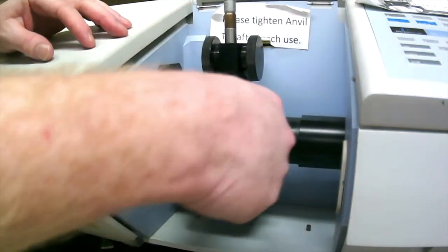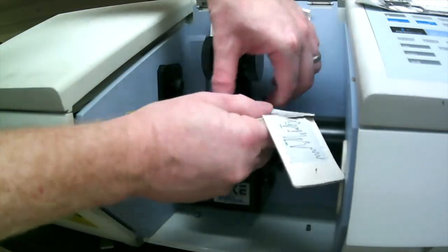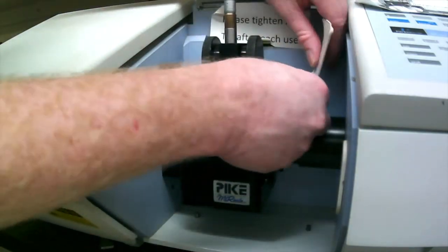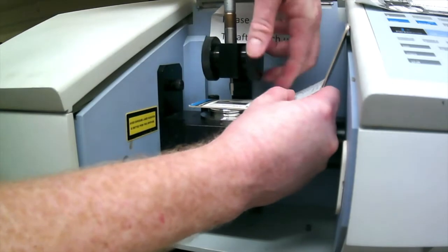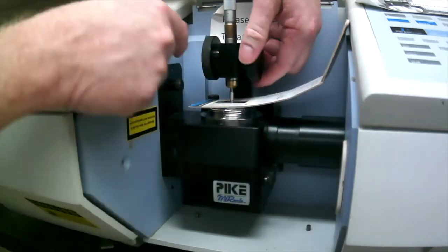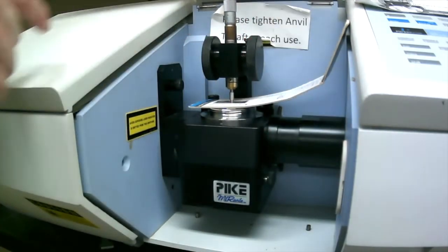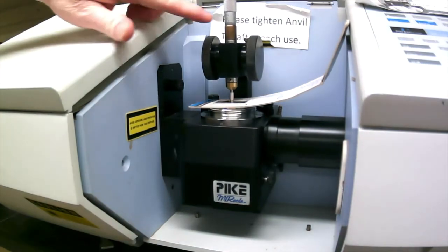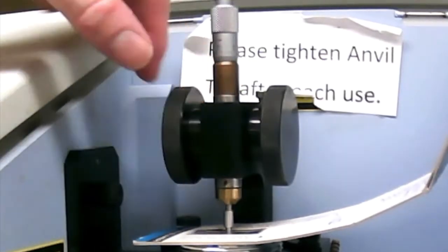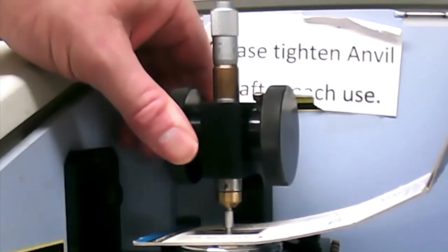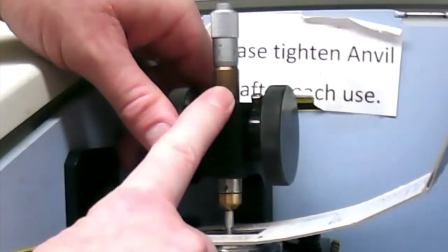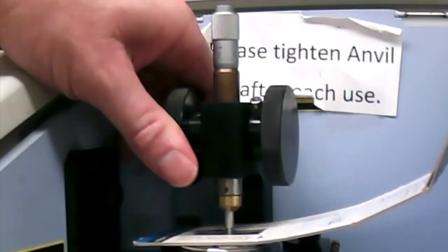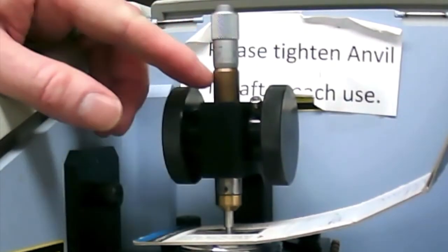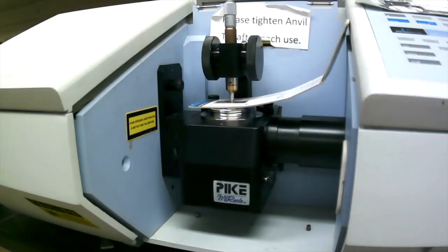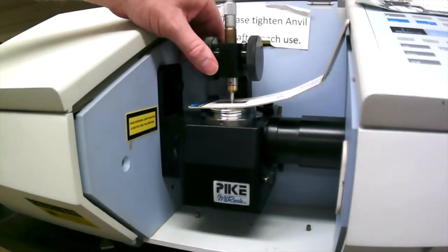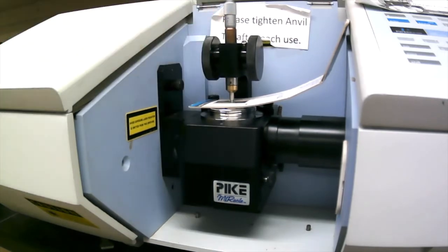So I'll put this on here. And the polystyrene, it's not in contact enough with the zinc selenide crystal currently. So I have to twist this anvil down. And as I'm twisting it down, watch carefully how there's copper here and then stainless steel. You have to get the stainless steel almost completely encased in the black thing there. So if you can barely just see a little silver lining, y'all on camera, you probably can't see it. Now it's down enough. You have to give it a fair amount of pressure, otherwise this won't work.